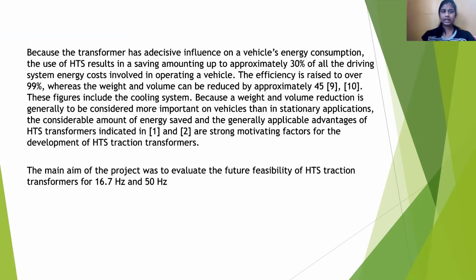Because the transformer has an influence on a vehicle's energy consumption, the use of HTS results in a saving of up to approximately 30% of all the driven system energy costs involved in operating a vehicle. The efficiency is raised to over 99%, whereas the weight and volume can be reduced by approximately 45%. These figures include the cooling system, because a weight and volume reduction is generally considered more important on vehicles than in stationary applications.